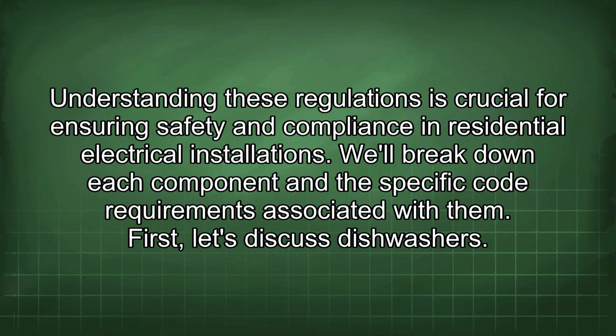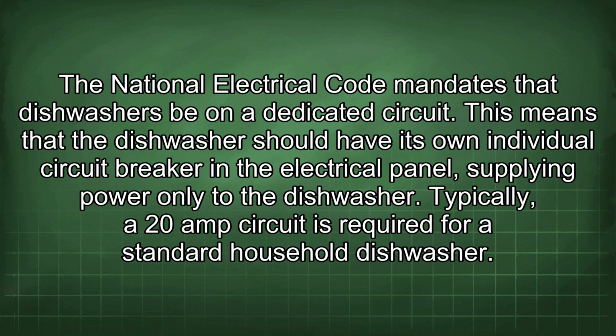First, let's discuss dishwashers. The National Electrical Code mandates that dishwashers be on a dedicated circuit. This means that the dishwasher should have its own individual circuit breaker in the electrical panel, supplying power only to the dishwasher. Typically, a 20-amp circuit is required for a standard household dishwasher.